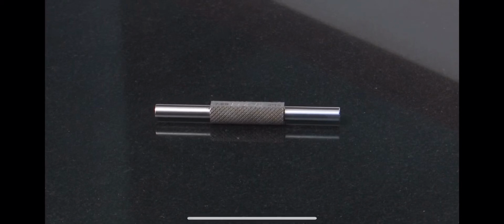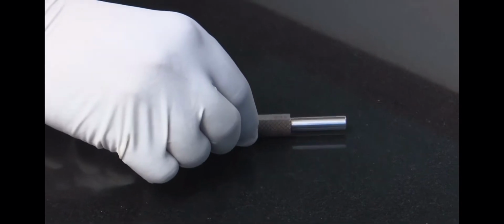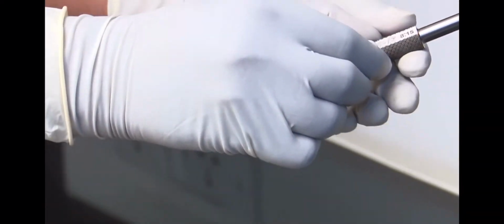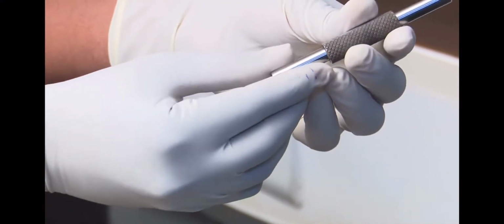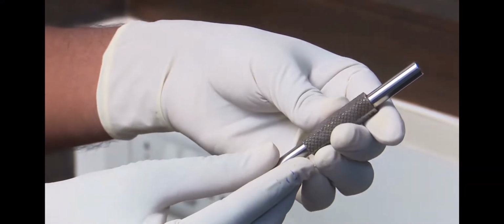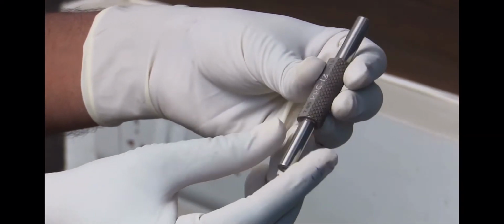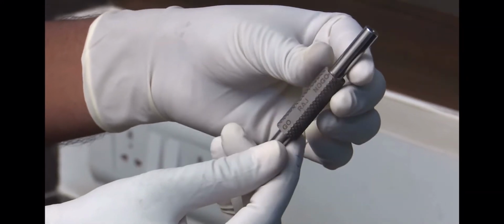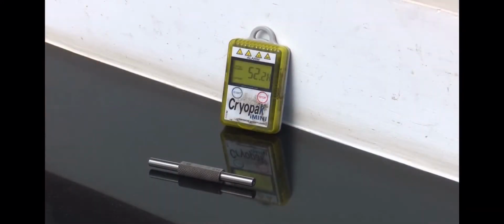Here I am demonstrating live display of step-by-step calibration method for plain plug gauge. After cleaning, visually inspect the plain plug gauge for any physical damage or rust, etc. Keep the plain plug gauge for at least 30 minutes for soaking at 20 ± 2 degrees centigrade so that the temperature is brought to equilibrium.